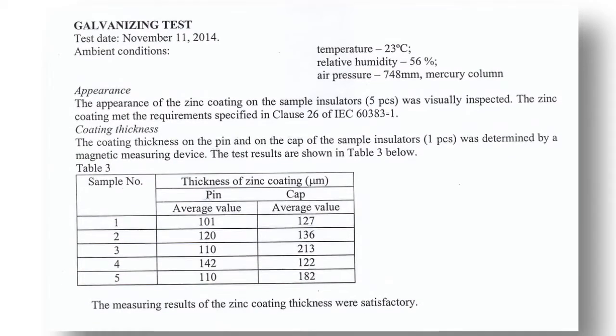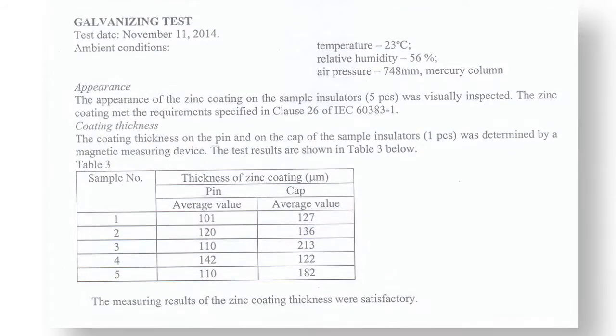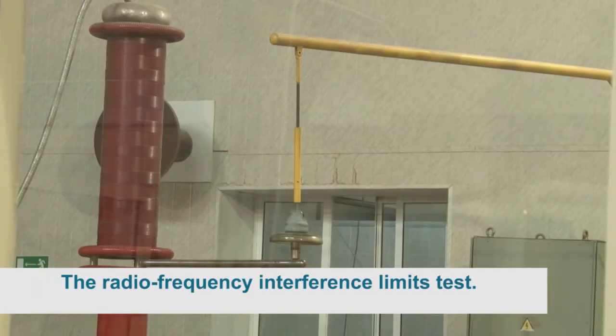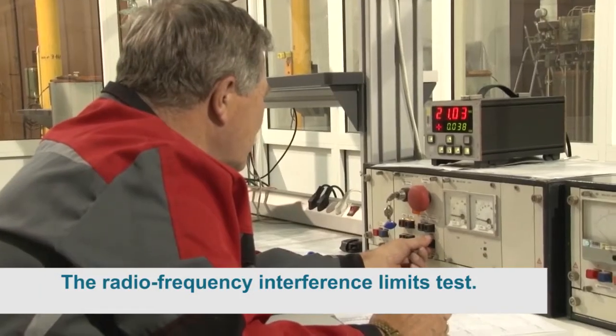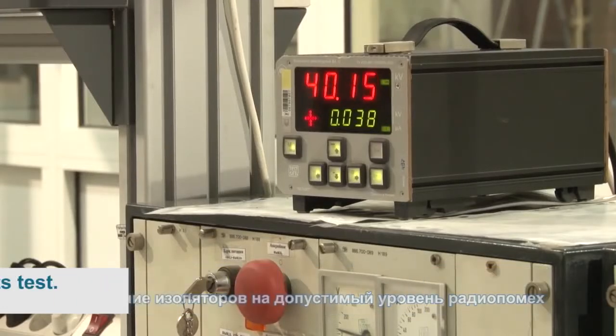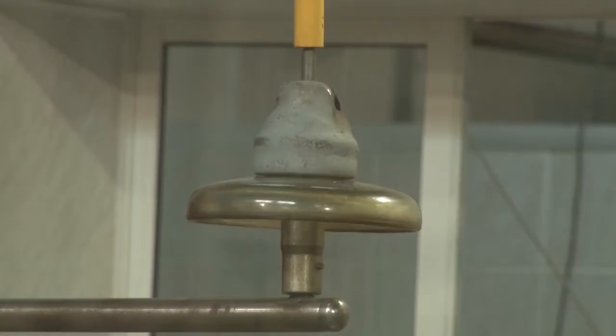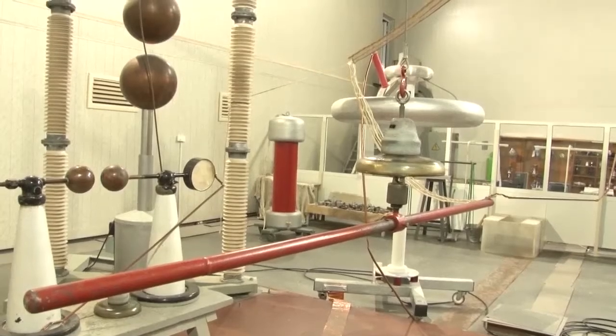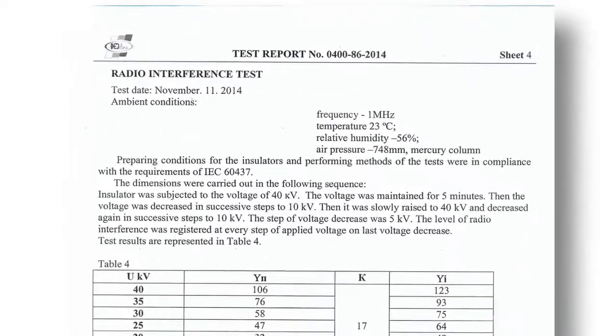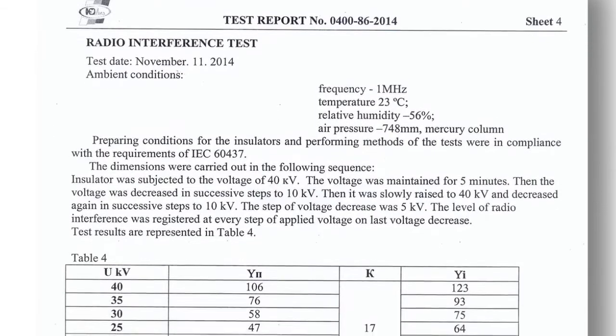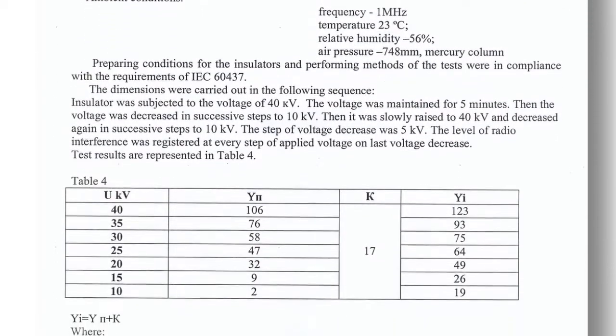The radio frequency interference limits test of PS12A and PS70E types of insulator. The interference level did not exceed the accepted level under the limit test voltage. The step-like rise of the interference level under voltage increased up to 110% of the standard test voltage is absent. Insulators meet the IEC requirements.